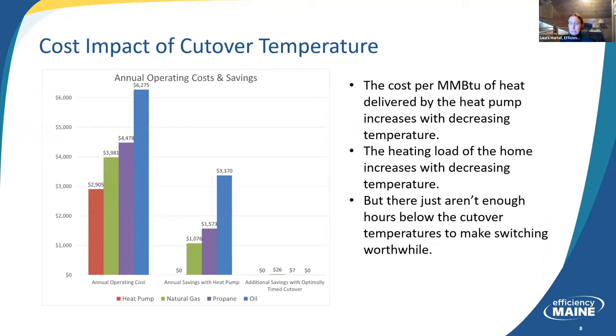So you can see that the heat pump is the least expensive system to operate. And this is assuming heating the whole home all winter long in Caribou, right? We're still talking about Caribou. In the middle there, you see the cost difference between operating those other systems and a heat pump. So if you ran a heat pump rather than a natural gas boiler, you would save $1,000 a year. Against propane, it's about $1,500, $1,600. And against oil, it's almost $3,400.